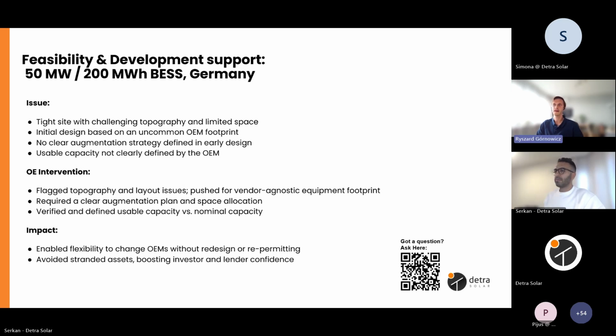Another important intervention was to verify that design assumptions were based on usable capacity and not marketing nameplate values. This was a crucial finding, as nameplate values rather than usable capacity had been assumed in the system modeling. Lastly, we highlighted the importance of defining the augmentation strategy early on to ensure space is allocated for it on site. By addressing those points upfront, we allowed flexibility to switch vendors without major layout updates, potentially avoiding costly and timely redesigns, and gave lenders confidence the system would meet performance expectations over its lifetime.